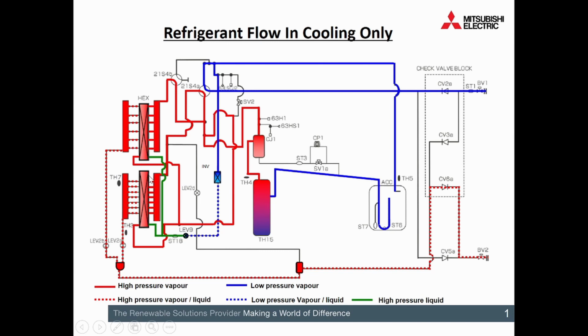Now how we decide the actual condensing temperature that we want to work with here is it looks at TH7, which is our ambient temperature reading, and it aims for that to be 10 degrees above that temperature. Therefore we can give off that heat. That's the whole point. Therefore we're condensing. That's also been used as part of the actual fan speed control, to control the head pressure control.